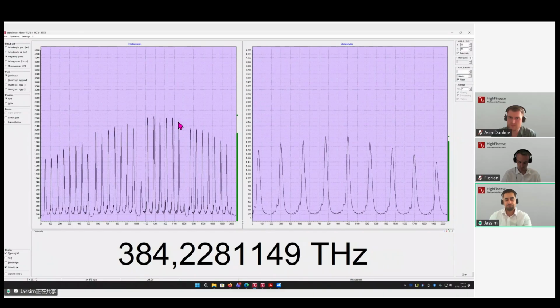And you could see, for example, that there are several interferometers, not one, and this is usually shown by these small sections here. So here you can see there are 4 interferometers, and here we have one long one. In the horizontal axis, these are the pixel numbers of the CCD array, and in the vertical axis, this is the intensity in arbitrary units. And you will be able to see when these interferogram peaks are high or low, this will give you an idea if your measurement is about to be overexposed or underexposed.